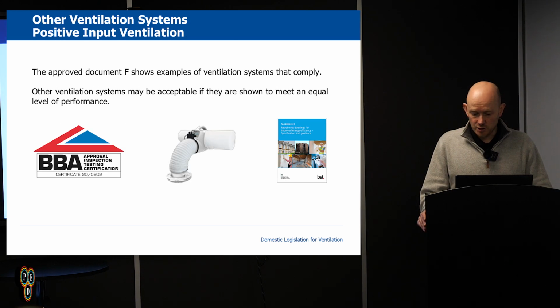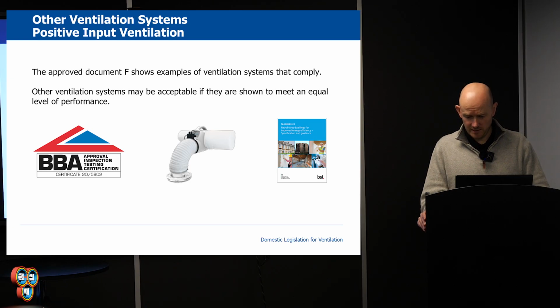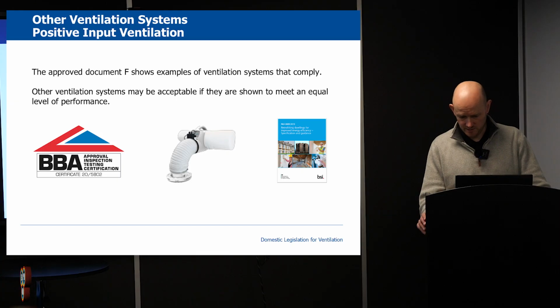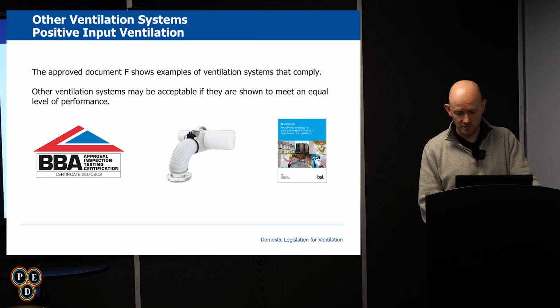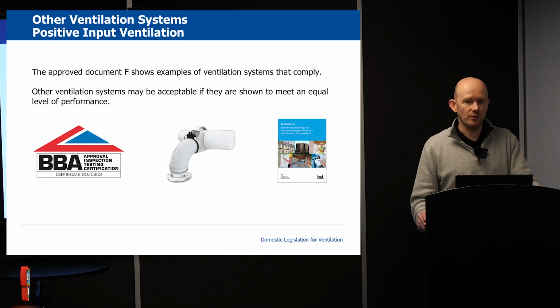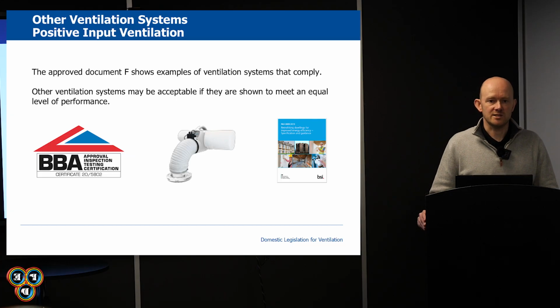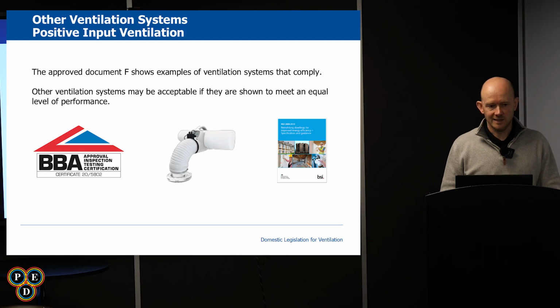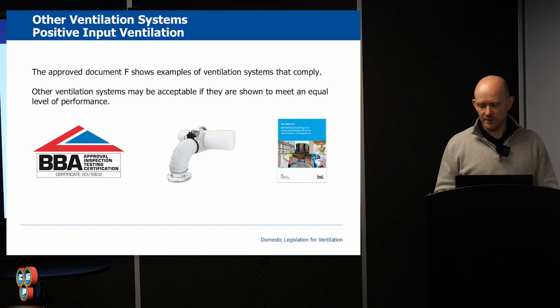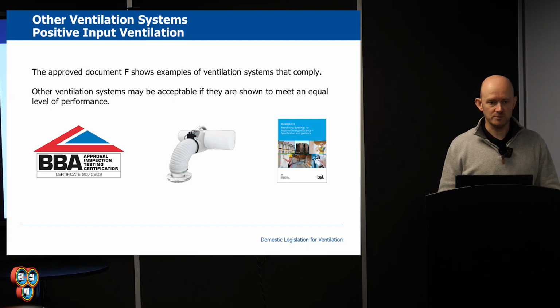Part F shows examples of ventilation systems that comply. Alternative ventilation systems such as PIV may also be used, provided it can be shown to have an equal level of performance. This may be demonstrated through expert guidance, and should include use of BBA certification or following the BSI PAS 2035, which is considered the most adequate means of demonstrating compliance. So yet again, this is a build that may have wanted MVHR, but the consultant has messed up the design. You can't get it in the property, and you need another means of bringing air in. There are retrofit standalone products called PIVs that can bring air into the property, but it's very rare that we will go down that route. These PIVs are designed for old retrofit houses, problem solvers basically.